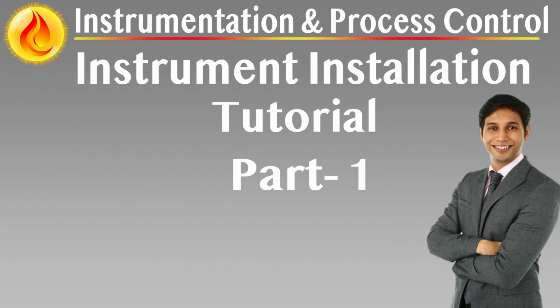Conclusion: designed for containment, access, and reliability. The design of instrument process connections must support precise measurement, safe access, and leak-free service under all process conditions. Every connection, whether isolated, flanged, or threaded, must be configured with consideration for fluid dynamics, solids carryover, and operational safety. Proper tapping orientation, high-quality sealing practices, and mechanical clearances are all essential to maintaining long-term measurement reliability and minimizing maintenance risk. Remote and direct mounting connections, engineering for modular integration and compact efficiency.